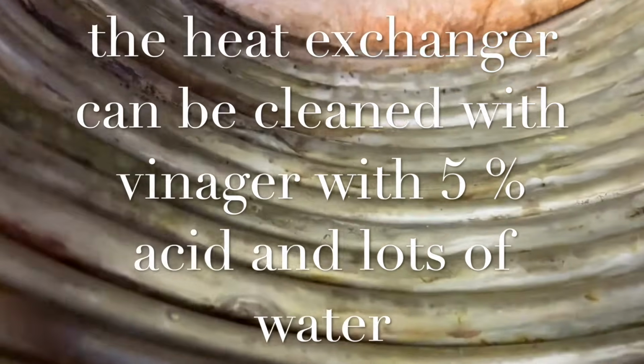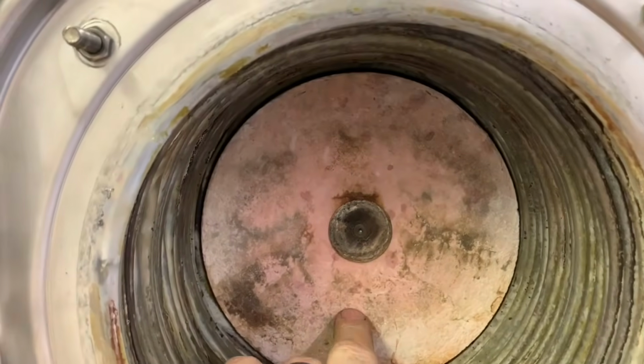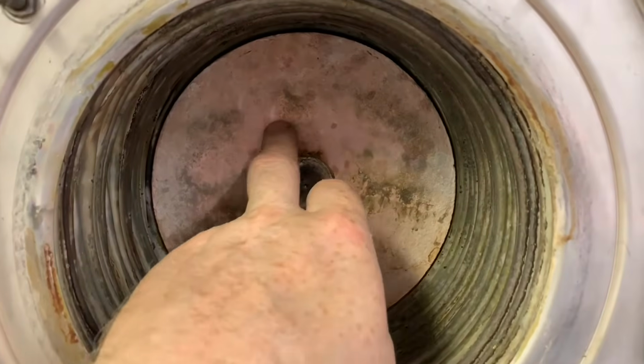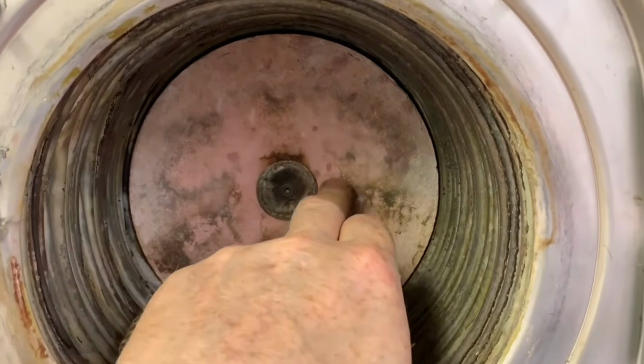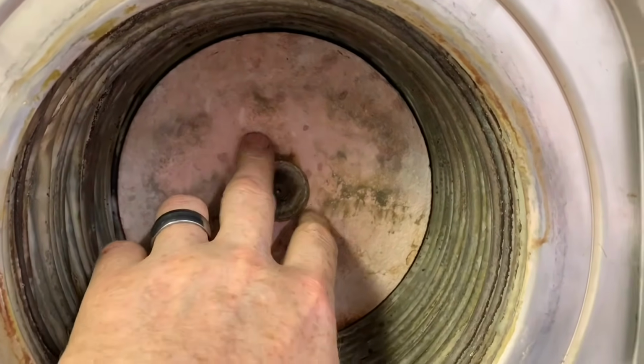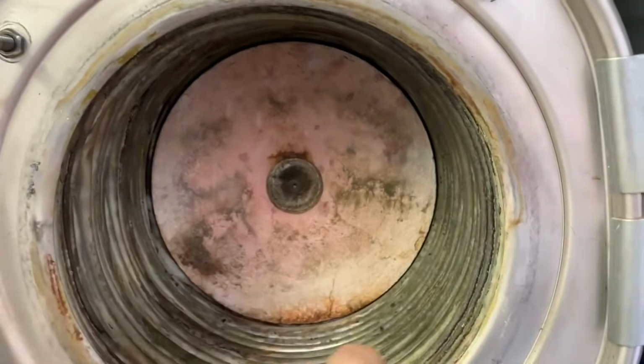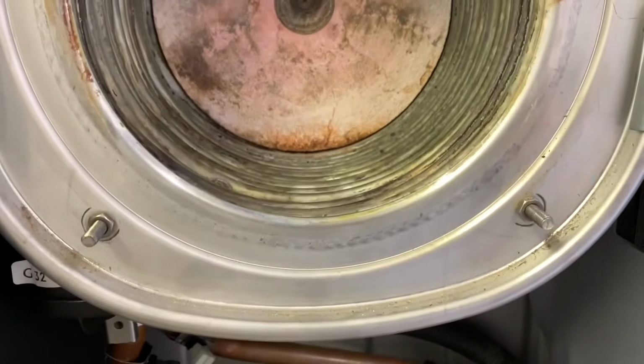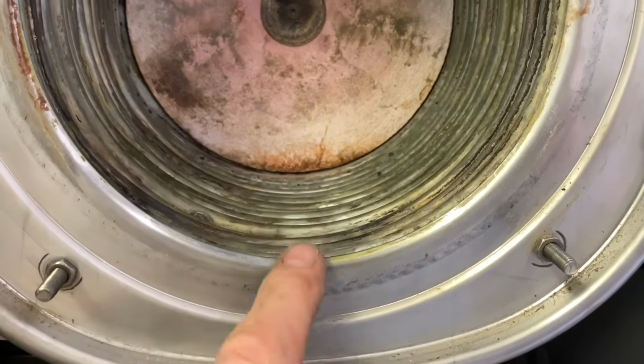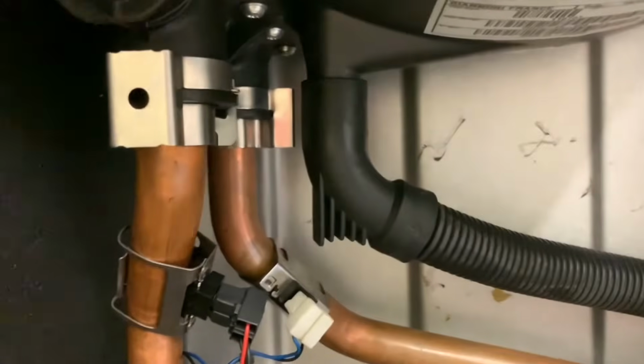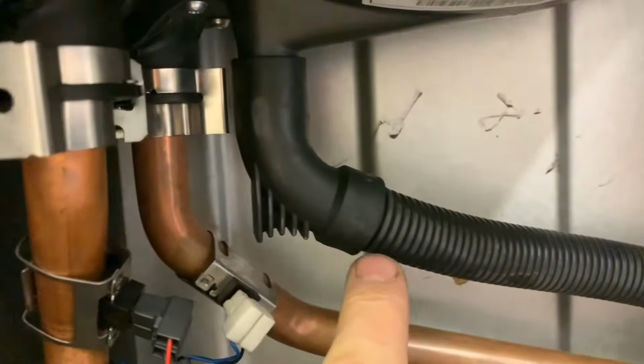So you can see how close they are together, and we need to make sure that they're all clean and the products of combustion can get through, because they actually go through those gaps. This again is another heat shield on the back here, and this is actually where the cup burner touches. So the cup burner goes right the way to the back and burns 360 degrees around here. The condensate then drops down to the bottom and then comes out through this tube here.